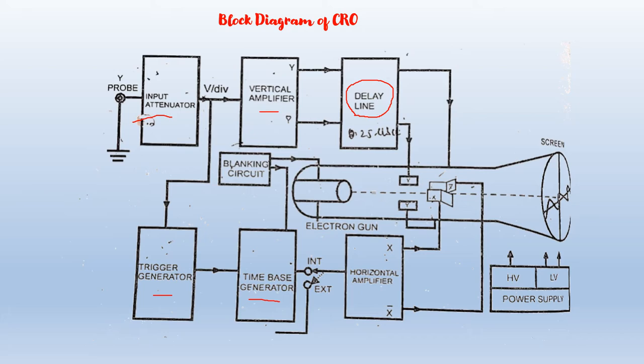The next block is the Horizontal Amplifier. This amplifies the sawtooth voltage. As it includes a phase inverter, two outputs are produced — a positive-going sawtooth and a negative-going sawtooth — which are applied to the right-hand and left-hand horizontal deflection plates of the CRT.